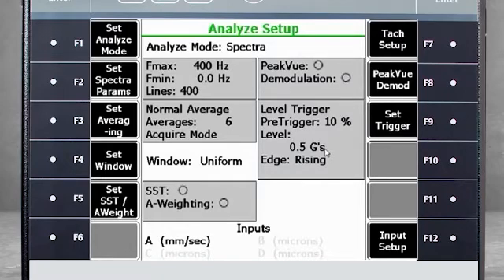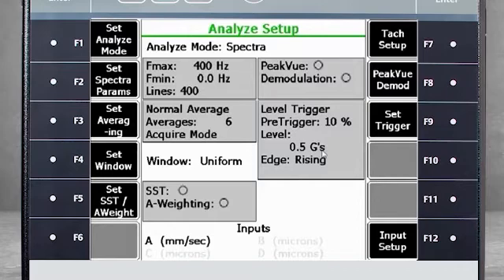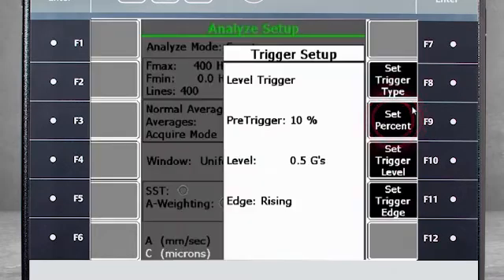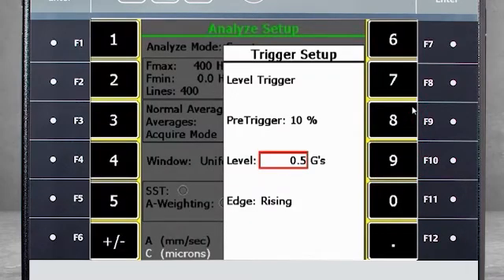This is where the exceptions come into play. The first exception occurs if there is already a lot of background vibration near the machine and it is higher than 0.5 Gs. This will cause the analyzer to recognize a false trigger and store bad data. To correct this situation, simply select F9 Set Trigger, then F10 Set Trigger Level. In this example, I am changing to 2 Gs, which should be sufficient.